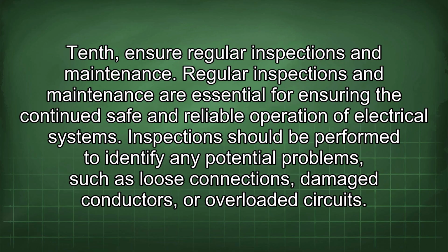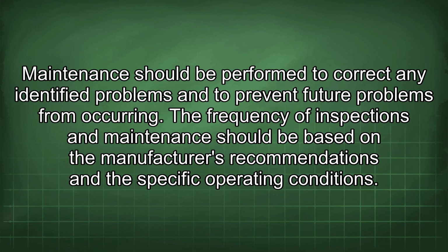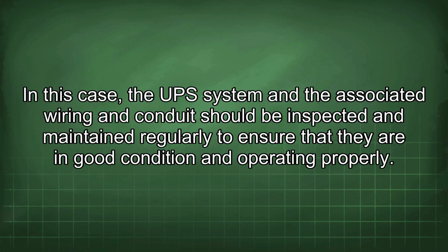10th, ensure regular inspections and maintenance. Regular inspections and maintenance are essential for ensuring the continued safe and reliable operation of electrical systems. Inspections should be performed to identify any potential problems, such as loose connections, damaged conductors, or overloaded circuits. Maintenance should be performed to correct any identified problems and to prevent future problems from occurring. The frequency of inspections and maintenance should be based on the manufacturer's recommendations and the specific operating conditions. In this case, the UPS system and the associated wiring and conduit should be inspected and maintained regularly to ensure that they are in good condition and operating properly.